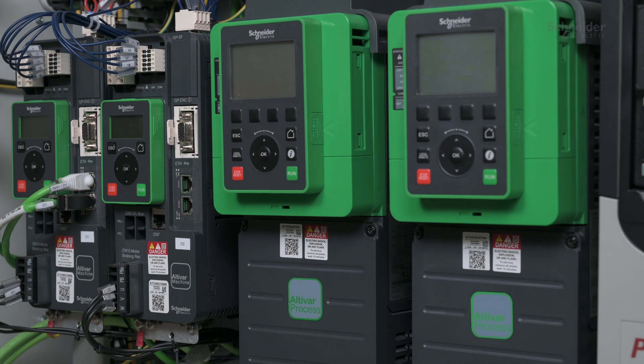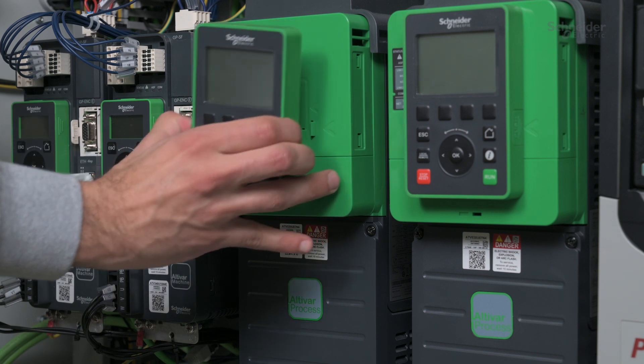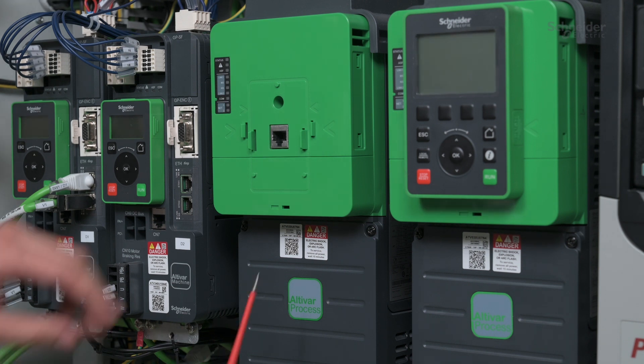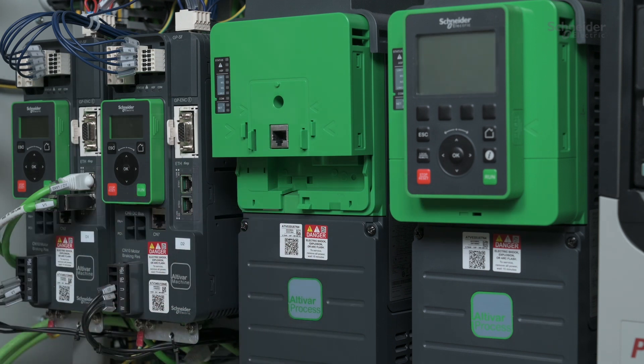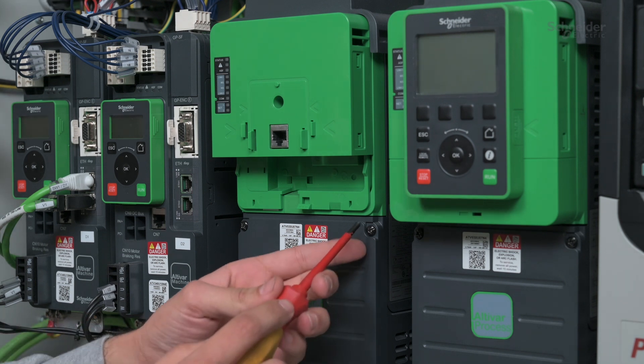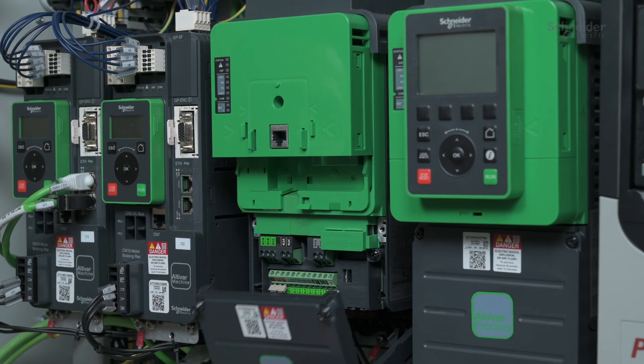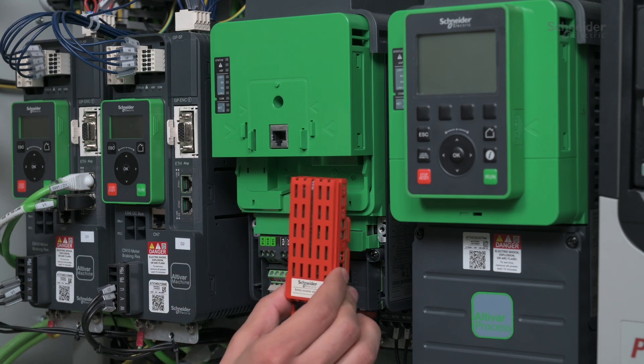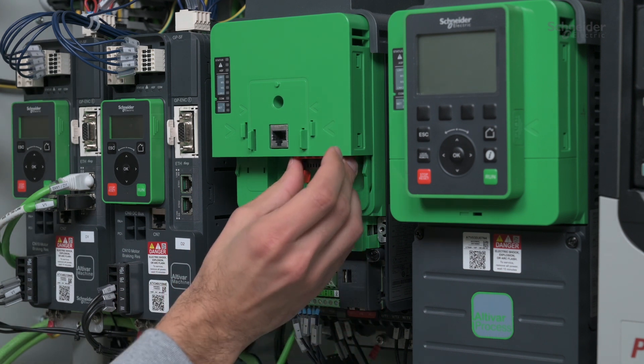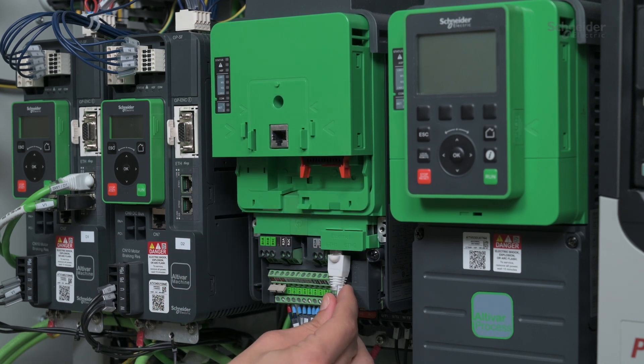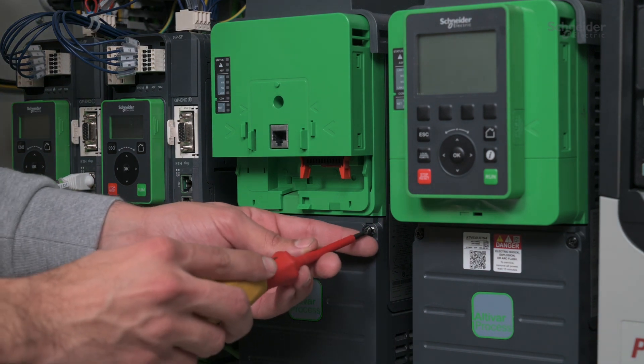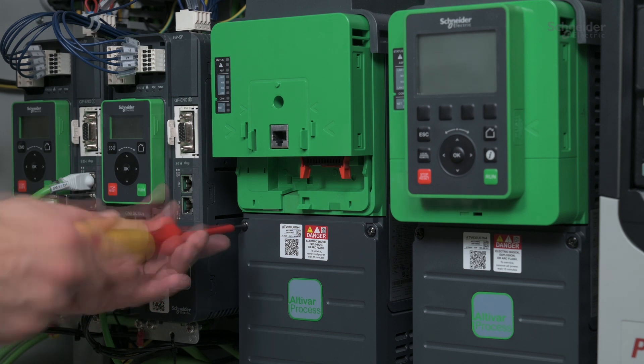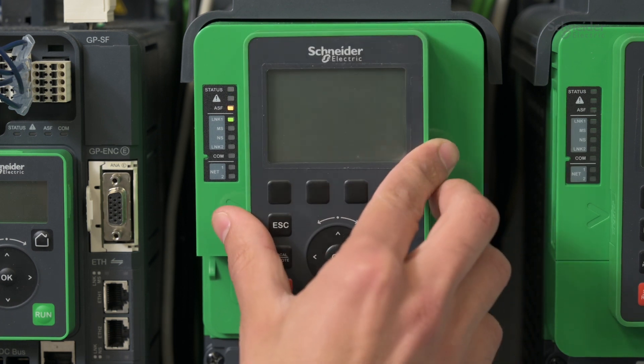Insert SIP Safety Module for Altivar as per the SIP Safety Instruction Sheet. First, we will show you the insertion with ATV900, then with ATV340. For ATV900, remove the graphic display terminal and the inferior part of the additional module support. Unscrew the four captive screws and remove the cover. Insert the SIP Safety Module. Connect RJ45 cable coming from M580 Safety PLC to Altivar Drive. Re-fit the cover by screwing the four captive screws. Re-connect the graphic display terminal.